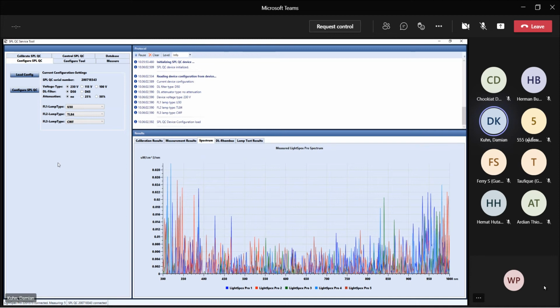So these are really configured at the factory with a factory service, with a factory SPLQC software, or they can get configured with the SPLQC service software. And basically, whenever you hit that configure SPLQC button, this is going to download the light sources available in your actual SPLQC service software. So basically, if I look at the drop-down menus here, these are all the light sources that I'm going to download to this connected device if I hit that configure SPLQC button. So just ensure that you first load it so that you have your current setup. But then if you click on configure SPLQC, it will download these available light sources for all the 3 fluorescent lamp positions, and that will give the customer later on this instrument the option to select one of these light sources directly on the actual instrument.